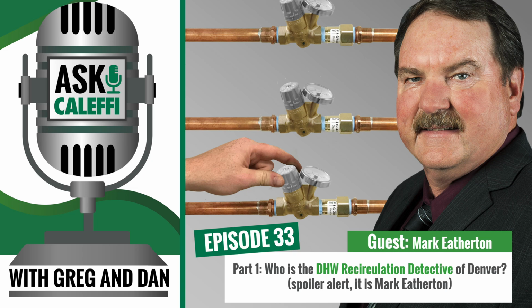Well, that one's a dead giveaway. That's a circulation return that's back charging. And people will say, well, but the pump is running. It shouldn't be able to do that. Well, yeah, it shouldn't, but it is. We've actually gotten calls similar to that where they think it's the mixing valve that's doing that.